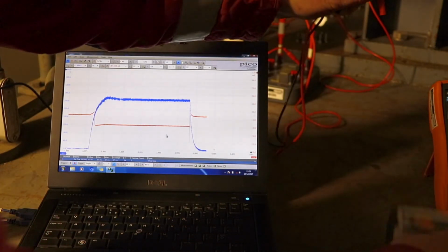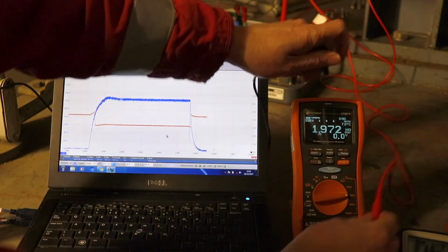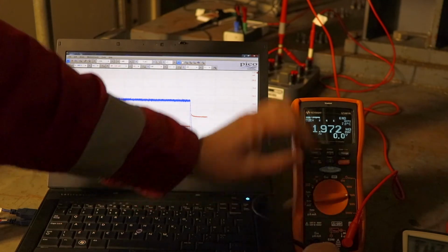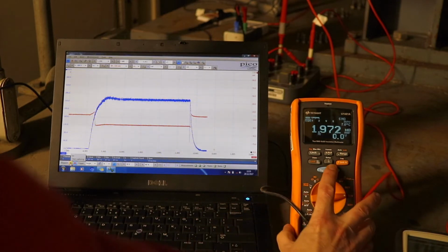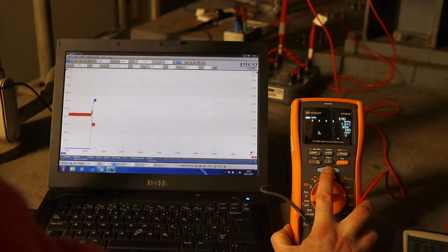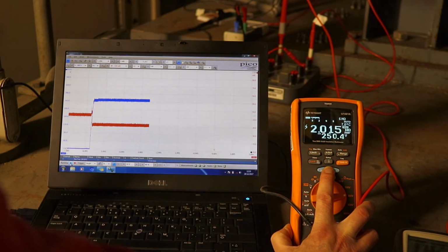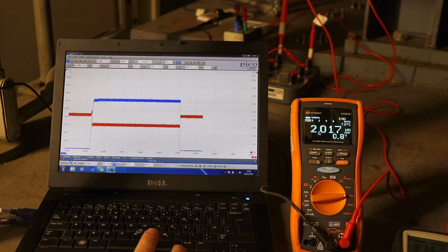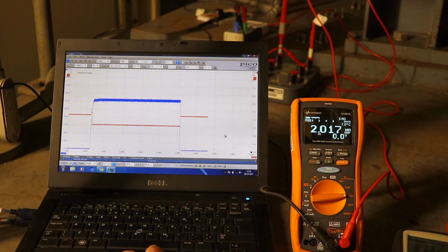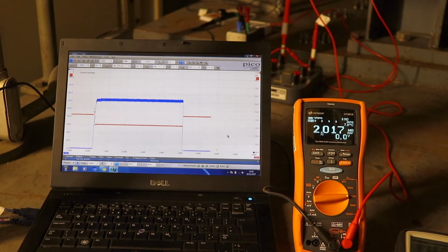Just swap the instruments over. I'll put it onto Keysight. I'll show what that one does. Okay. So you see a much more rapid rise coming from the Keysight. So whether the rapid application of the voltage from this unit creates the problem or not, I don't know. What I will do is repeat the test without the current shunt in there, so I get a proper reading from the voltage.